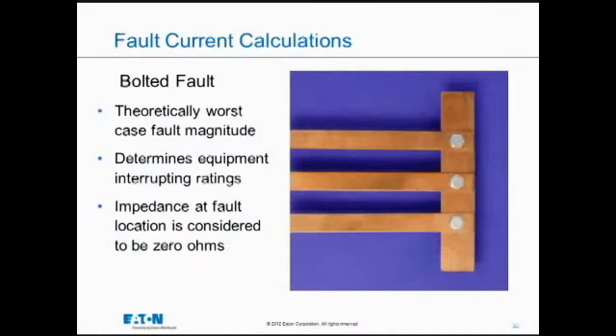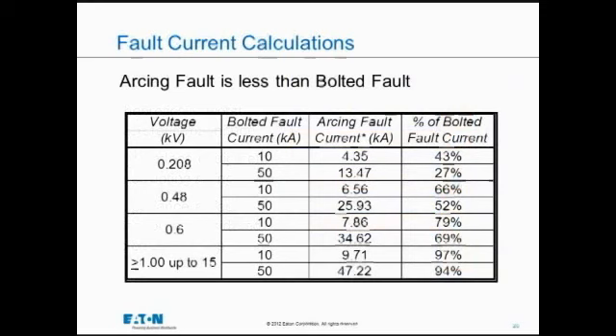So bolted fault, we connect it all together. It's the worst condition. And this chart is just showing how the fault current changes to a lower value from bolted. So the bolted fault is always higher than arcing current, and as the voltage gets higher and higher, as you go farther down on the chart to higher and higher voltages, the difference between bolted and arcing becomes less significant. So it's a much more significant change at 208 volts compared to, let's say, 600 volts, and it's almost insignificant above 1,000 volts, the change to arcing current.